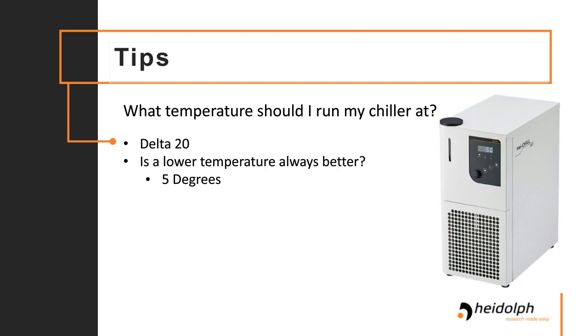Sometimes we get the question of what temperature should I run my chiller at. What's important to understand is that bringing your chiller temperature unnecessarily low won't increase the speed of your process. That's why it's important to follow the delta 20 rule. If your heating bath is at 60 and your vapor temperature is at 40, running the chiller below 20 degrees won't really speed up your process. So it's important to recognize that a lower temperature doesn't always lead to a better result. Sometimes running it at 5 degrees is just as effective as running it at -10.